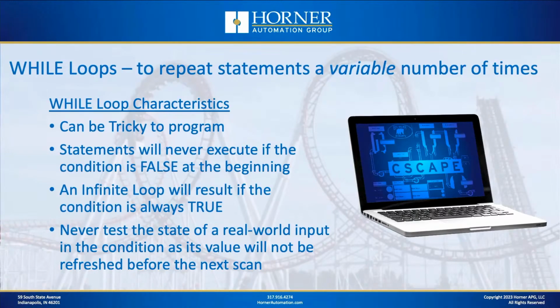It depends on, of course, what you're trying to accomplish. Also, the whole infinite loop is what you have to be careful of. So if your Boolean condition is always true and never goes false, then you're going to have an infinite loop. And if you include, let's say, a real-world input as part of your Boolean condition, then you're definitely at risk of an infinite loop as well, because keep in mind, real-world inputs are only updated or refreshed at the beginning of the scan, and loops always execute within the same scan. So if you're looking for a change in state of that real-world input as part of your condition, it's just not going to happen, and you probably are going to end up with an infinite loop.